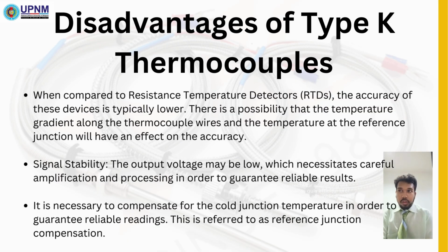The first one is accuracy. The thermocouple generally has lower accuracy compared to RTD. The second one is temperature gradient. Temperature varies along thermocouple wires and at the reference junction, which can affect the accuracy. The third one is signal stability. Output voltage is typically low and requires precise amplification and also processing. The last one is cold junction compensation. It is essential for accurate reading, compensating for the reference junction temperature.